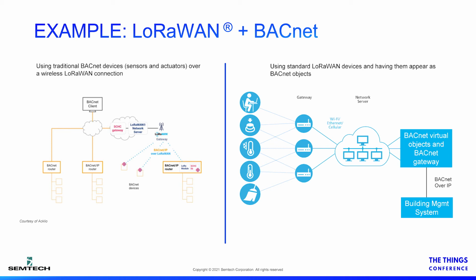The advantage of this approach is that you can augment a broad portfolio of existing BACnet-equipped devices to now include connecting these wirelessly. On the right is a method whereby data collected with standard LoRaWAN sensors—this is the opposite of the previous approach showing standard BACnet sensors—can be ingested into a building management system.